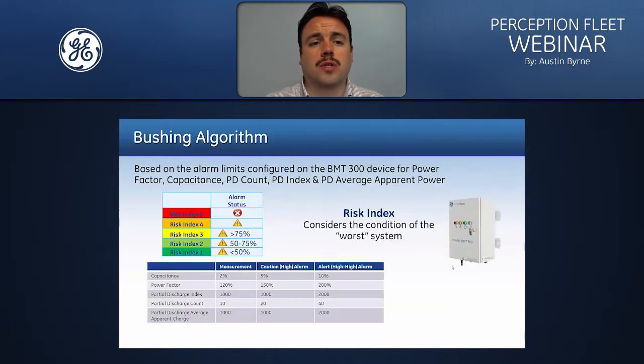Next, we're going to take a look at our bushing algorithm. The bushing algorithm is based on the alarm limits configured within the BMT300 device for power factor capacitance, partial discharge count, partial discharge index, and partial discharge average apparent power. When we look at these particular measurements within the bushing monitor, we're checking to see if any of the measurements that are taken are close to the alarm limits that are set.